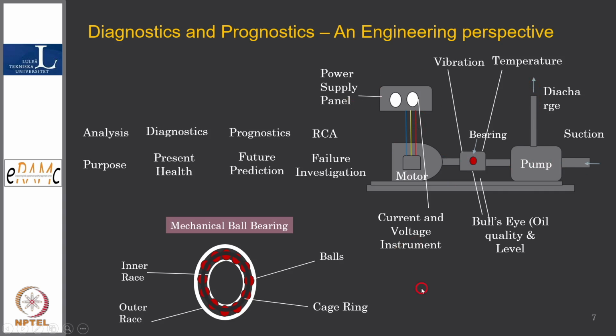This field is matured in the sense that using vibration signature or motor current signature analysis, we can find out what is wrong. These two white things are, one a voltage meter and the other a current meter actually, which give us information online. But during prognostics, we have to put some sensors over here for vibration and all that, because of radial, axial, shaft misalignment, bearing, as I told you, inner race, outer race, so many things you have to check. And for the motor, it is motor current signature analysis and so many other things.